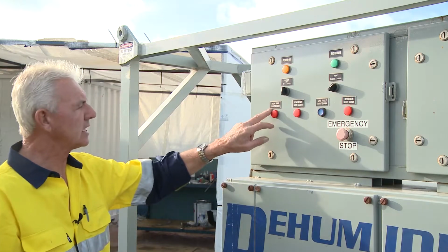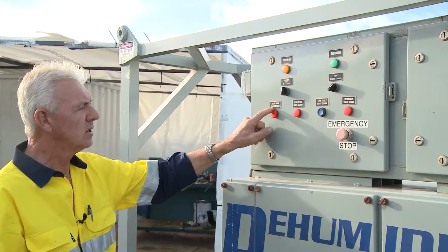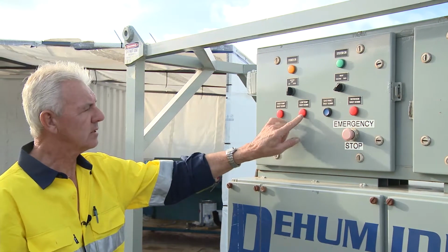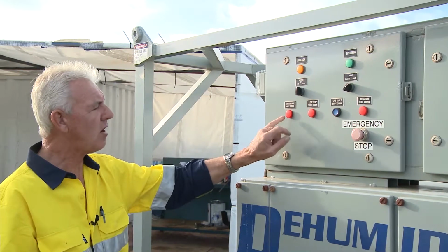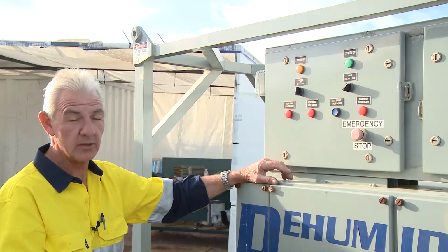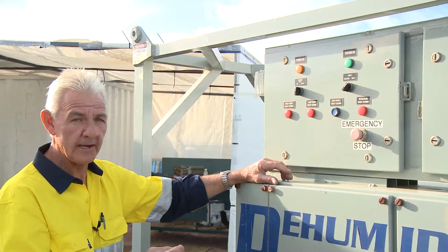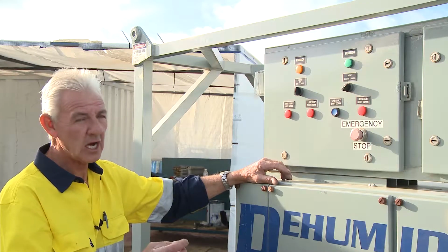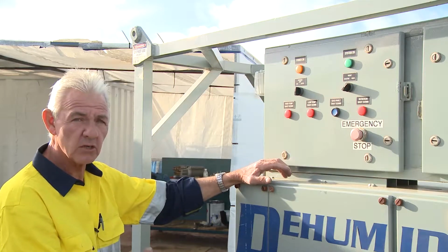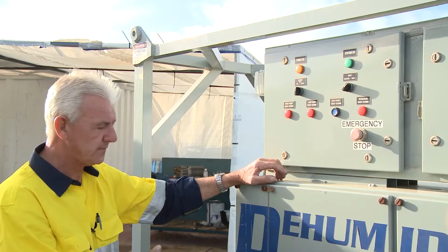So the labelling on this particular machine is relatively simple as far as low temp shutdown, high temp shutdown. What that means to you is when this particular section is illuminated, low or high, all it's telling us is that we've exceeded the temperature parameters within the cabinet itself, and thermostatically it's picked up that we've had a temperature spike. Is it a common occurrence? No. The only time you'll have high temp shutdown is if our filtration's blocked or the machine's struggling to pull the air through, and primarily that is the cause.